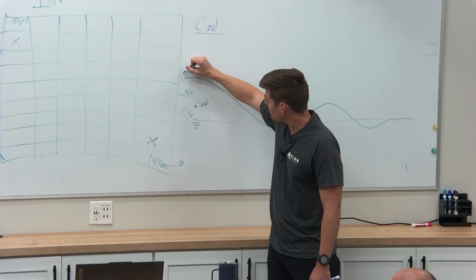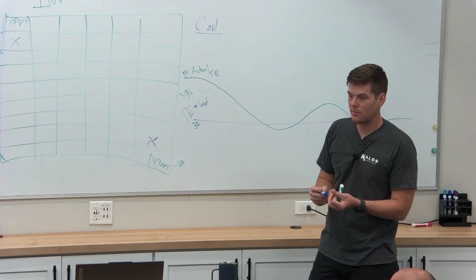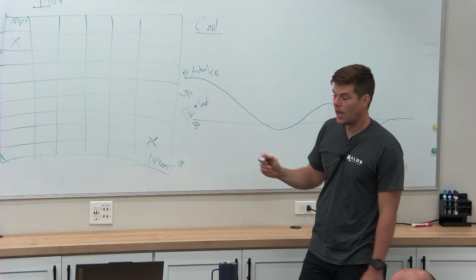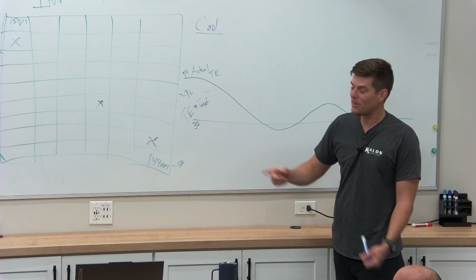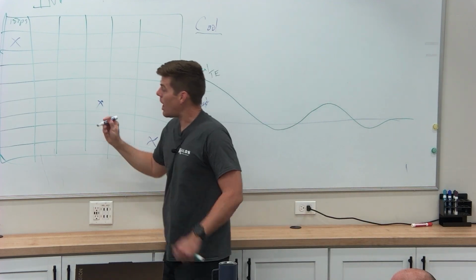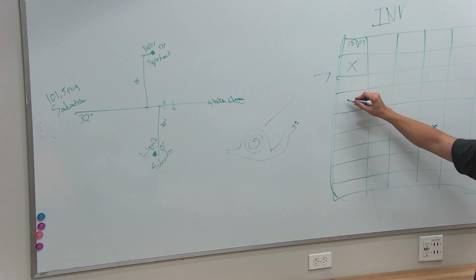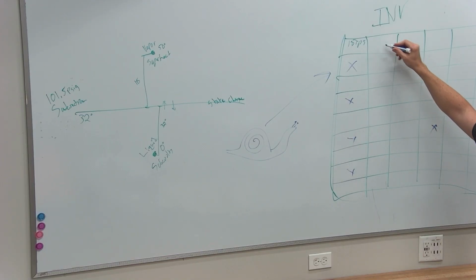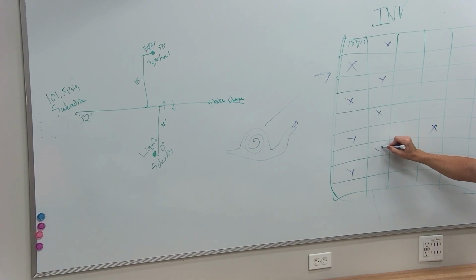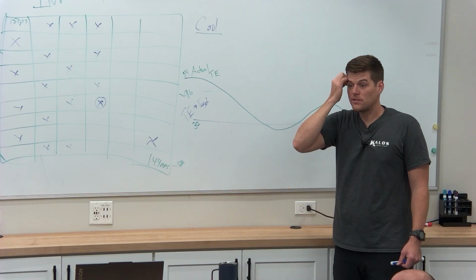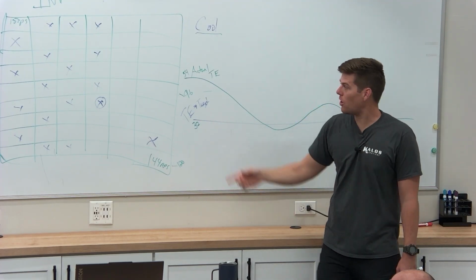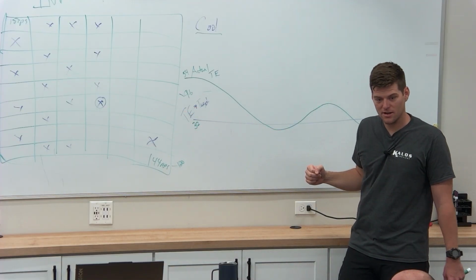What is it actually right now? Let's say it's 54 degrees. So what happens to my compressor? Yeah, it says J7. Speeds up. We go up on the bingo chart. And now it doesn't just jump to that speed. What it does is it goes here and then here and then here and then here. Remember, inverter systems are a slow ramp. It takes time. This could be 15 to 20 minutes before it finally arrives here. That's the natural progression of how inverters work. They don't go from here and then slam it into 6th gear, right? That's how we break stuff.